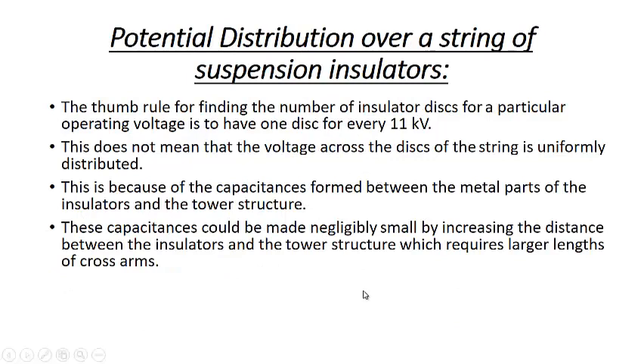Now we'll come to the potential distribution over the string of suspension insulators, and we'll see how this voltage is shared between them. Now the thumb rule for finding the number of insulator discs for a particular operating voltage is to have one disc for every 11 kV. But this does not mean that the voltage across the discs of the string is uniformly distributed. This is because of the capacitance formed between the metal parts of the insulator and the tower structures. So when this capacitance is formed, it results in a non-uniform distribution of the voltage across the discs.